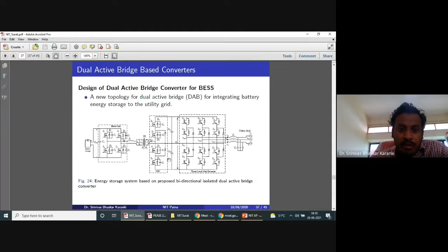When you talk about batteries, you should have bidirectional features, and it should also have isolation. Any problem on the battery side should not be reflected to the grid side, or any problem on the grid side should not be reflected onto the battery side. We have done some research on this, but if you ask pinpointly which is best, that depends on your requirement. If you are trying to inject very high power, I think dual active bridges are better.